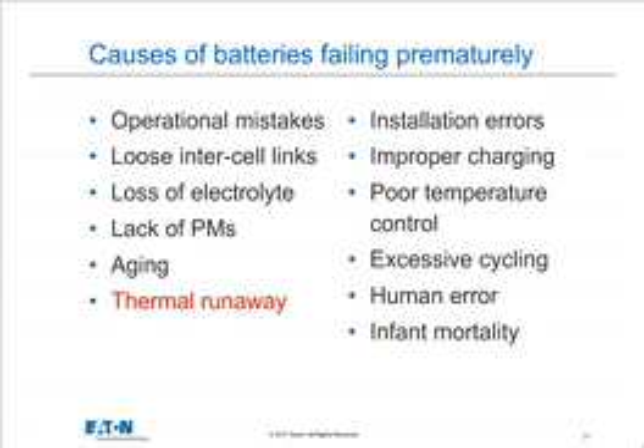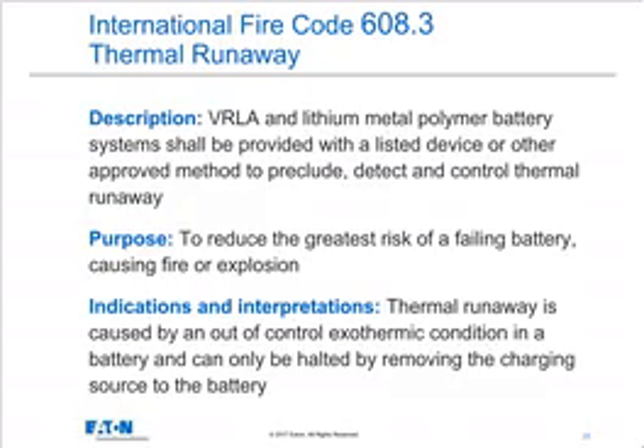The other kinds of things you see are installation errors, improper charging, excessive battery cycling. If you have an environment where you're running on batteries multiple times a day, every day of the week or the month or the year, that's going to have a very negative effect on battery service life. And of course, there's infant mortality. When a new battery is put in, it's possible that one of the jars or cells has been damaged in shipping or has another problem that causes it to fail early on. Okay, so how can battery monitoring systems help with this kind of thing?